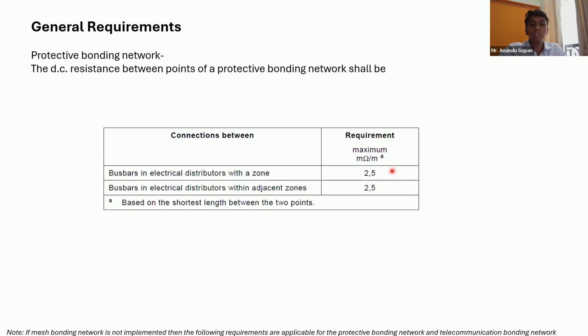We don't need to worry about high frequency impedance, just this DC resistance — and you can avoid it. If you cannot achieve this value, you have to go for a mesh bonding system, which we'll get to a little later. If you go for a mesh bonding system, you can avoid these requirements.